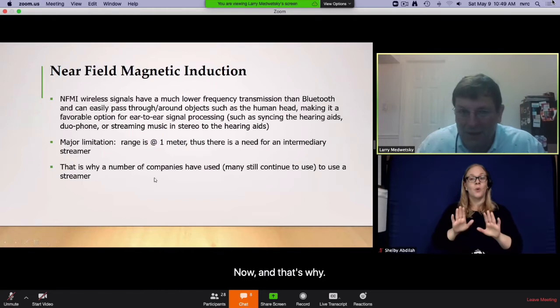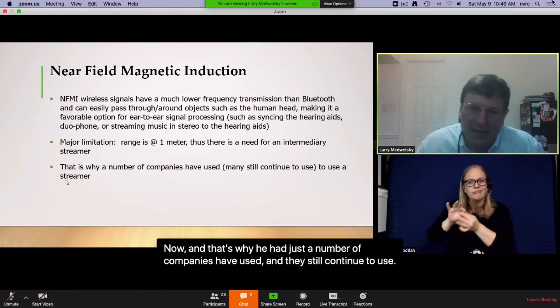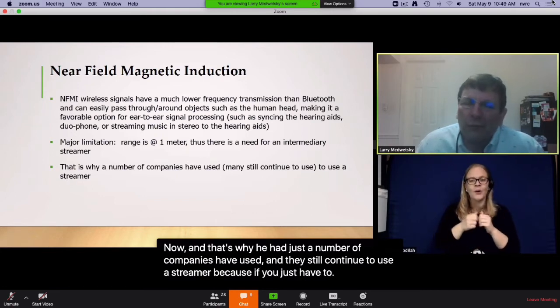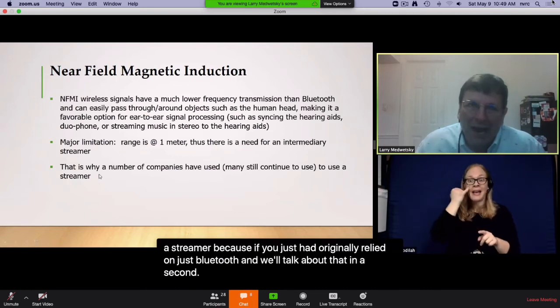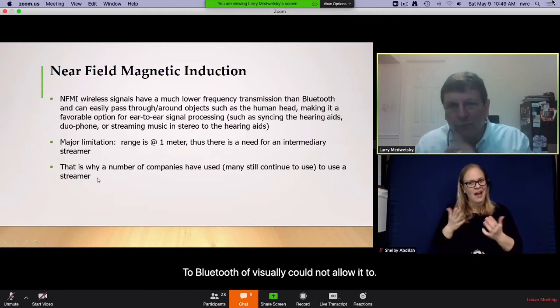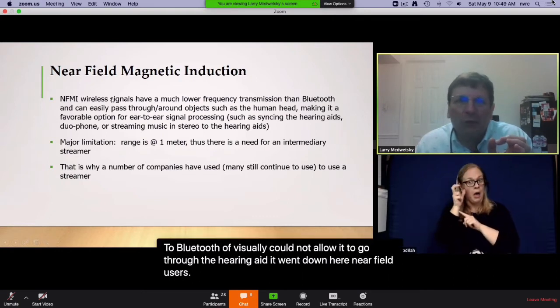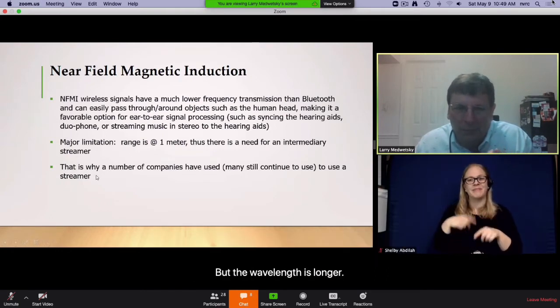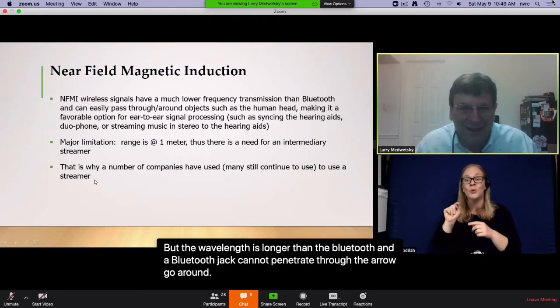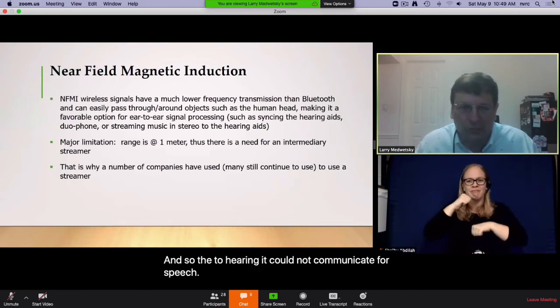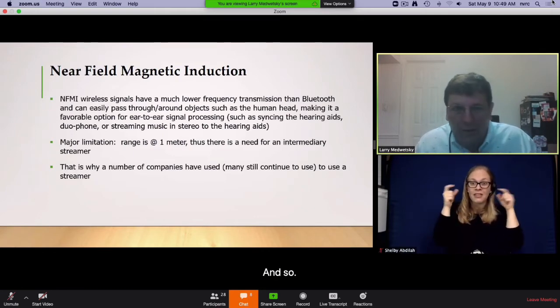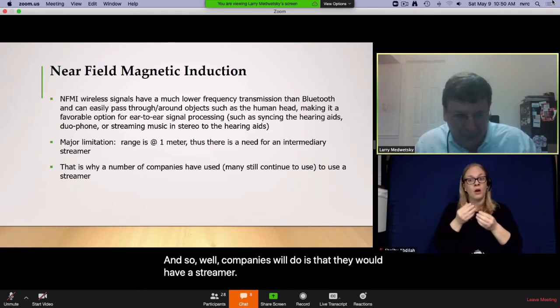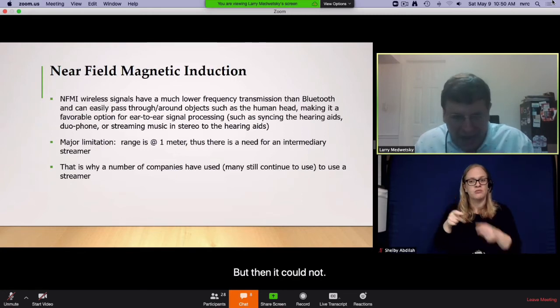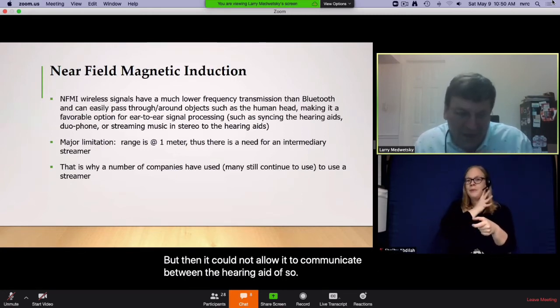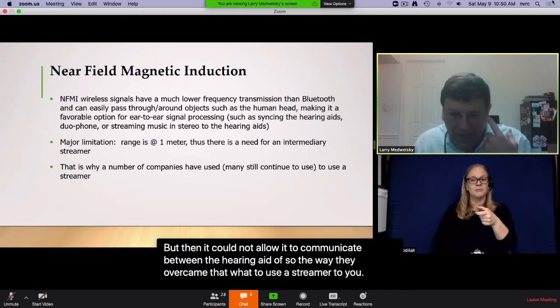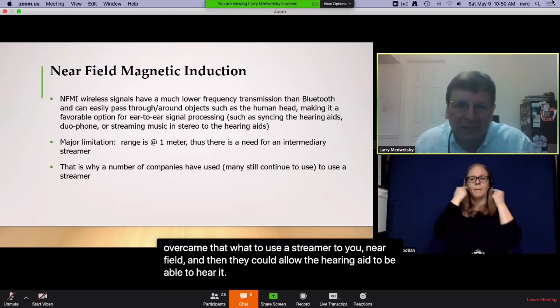Now, that's why a number of companies have used, and many still continue to use, a streamer. If you had originally relied on just Bluetooth, and we'll talk about that in a second, the Bluetooth originally could not allow it to go through the hearing aid. Near field uses about 10 megahertz, but the wavelength is longer than the Bluetooth, and the Bluetooth just could not penetrate through the head or go around it. And so the two hearing aids could not communicate for speech signals or any type of sound. So what companies would do is have a streamer that could pick up Bluetooth, but then it could not allow communication between the hearing aids. The way they overcame that was to use near field in the streamer, and then they could allow the hearing aid to be able to hear the acoustic signals.